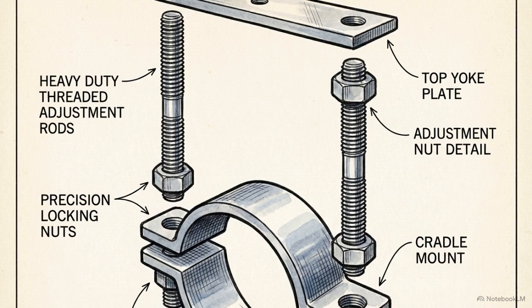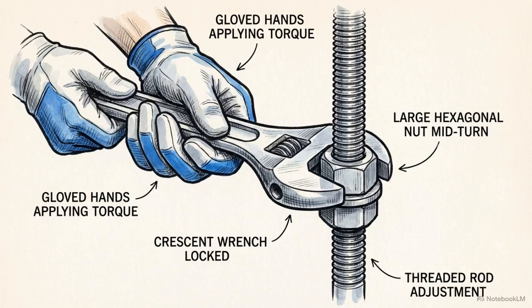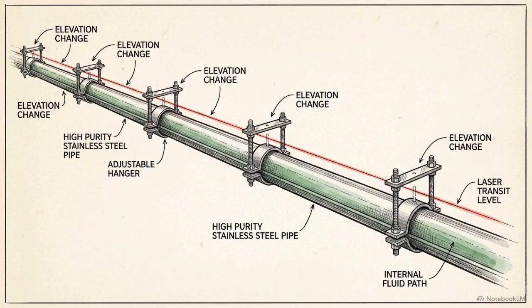These supports utilize threaded rods that allow for precise height calibration at every interval of the run. By tightening these hangers, a technician can lift a sagging pipe back into its 1% pitch without the need for cutting or rewelding. Correct hanger spacing combined with adjustable supports provides the necessary defense against the gradual loss of system slope. The final stage of correction is a physical verification test.